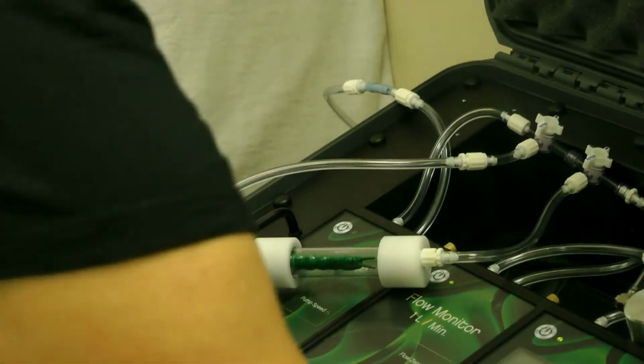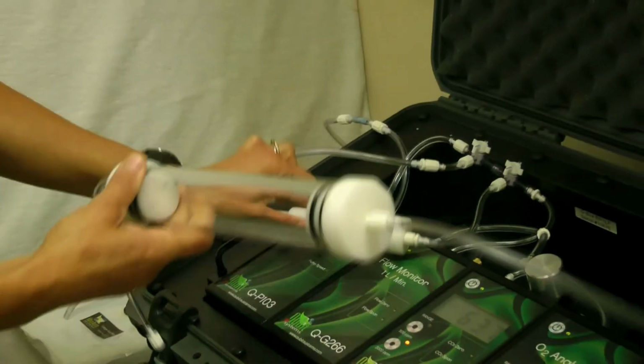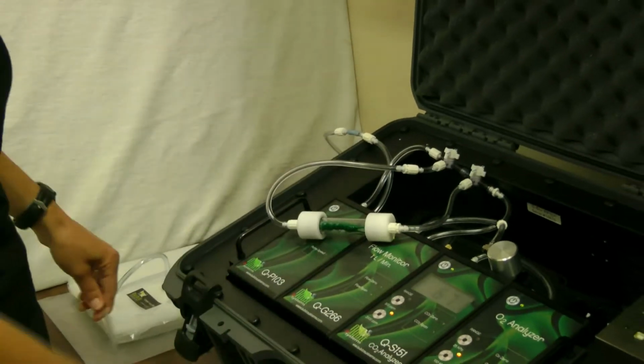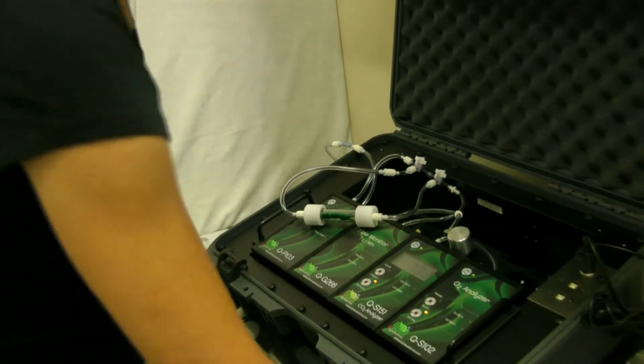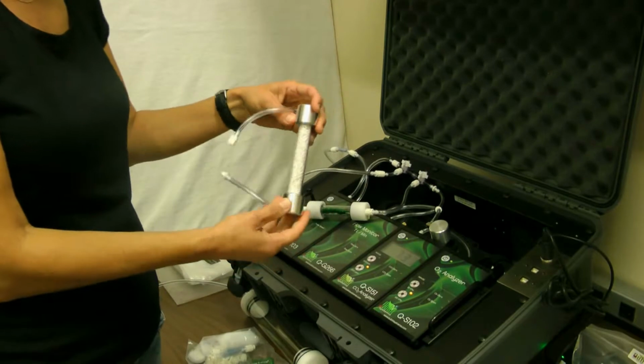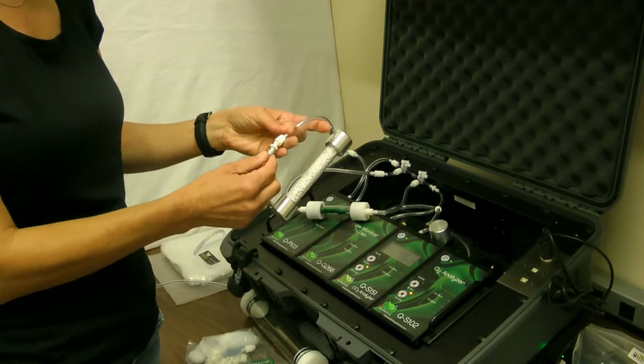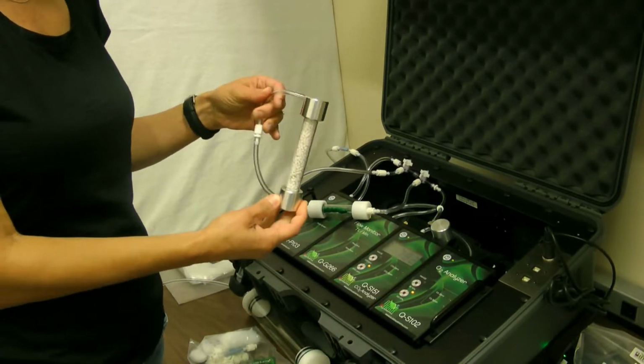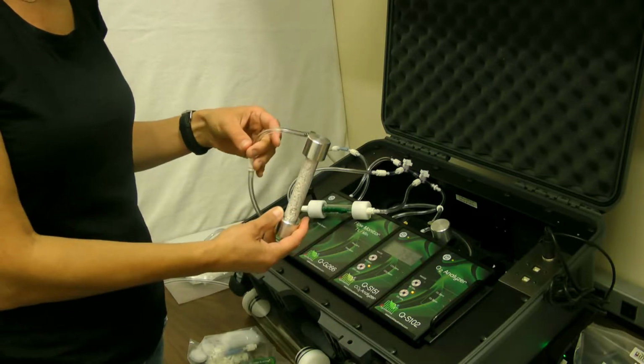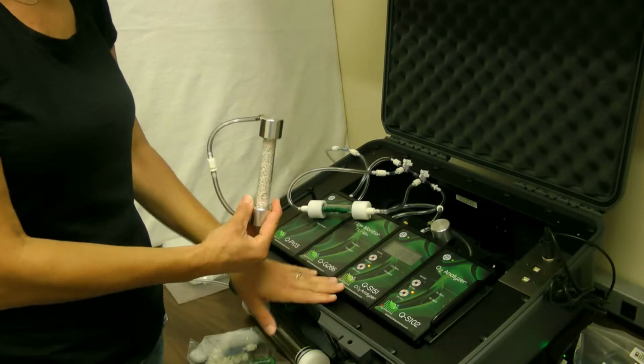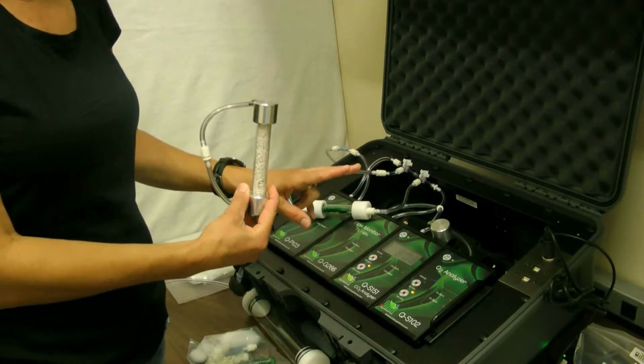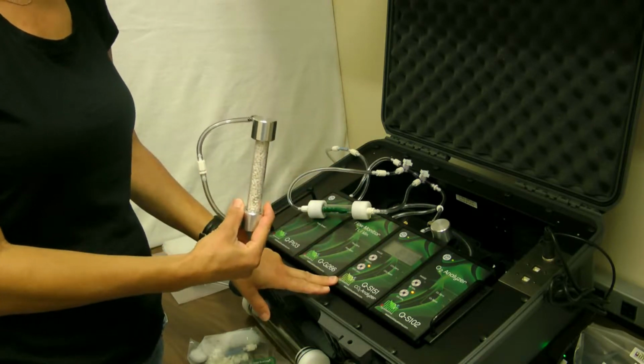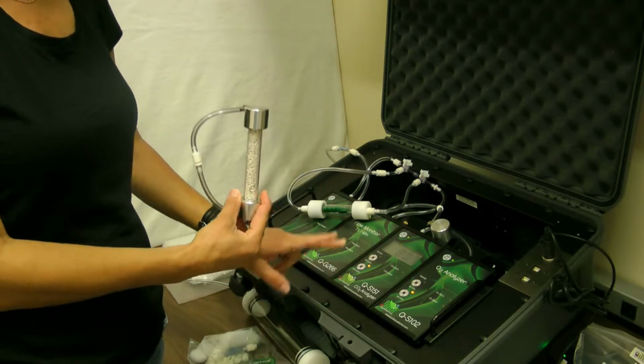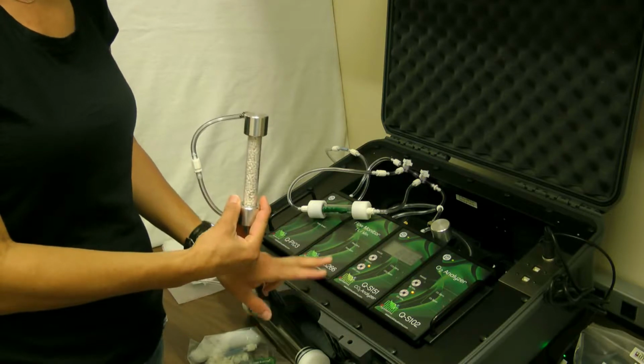There are 2 chambers provided with the system, a small chamber and a large chamber that I've already gone over. And there's also a soda lime column provided. The soda lime column is used to scrub CO2 from the air. So when you are doing calibrations of the CO2 analyzer, it's a 2-point calibration. The CO2 analyzer has a linear output. All you need is 2 points to calibrate it or to check the calibration.